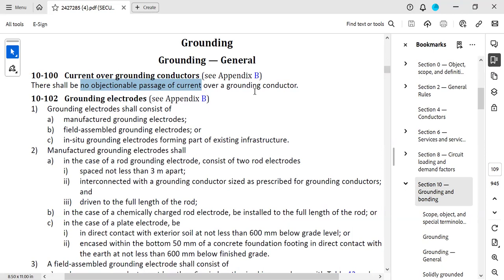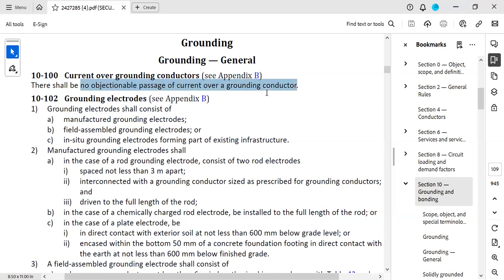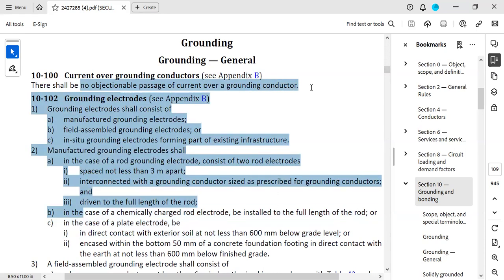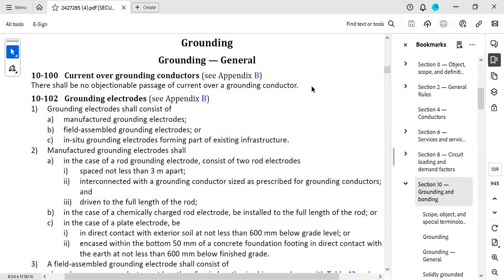Through the use of multiple grounds in a system, you might actually make an unbalanced neutral return current through the grounding conductor. That's objectionable because, again, no objectionable passage of current can move over a grounding conductor.